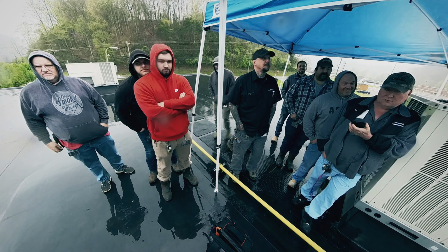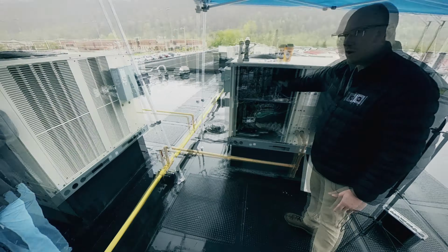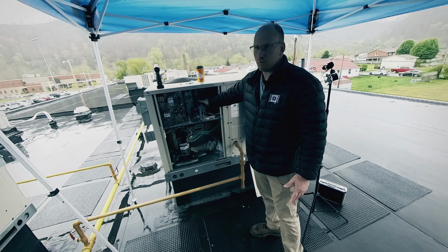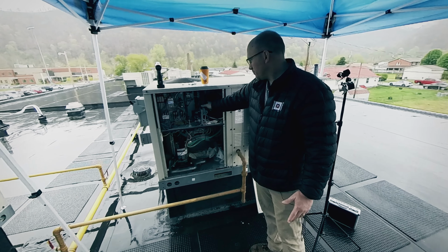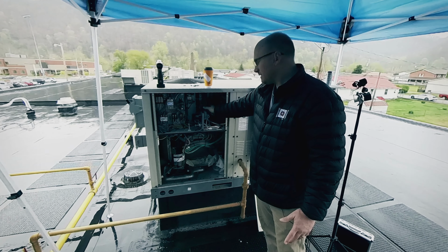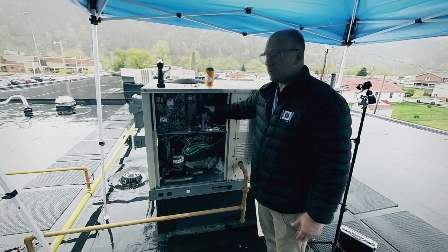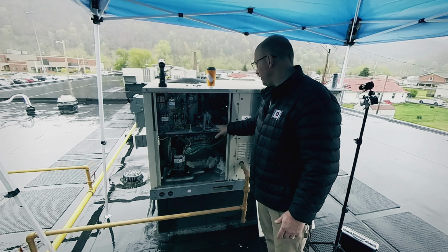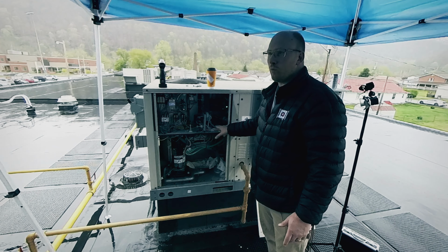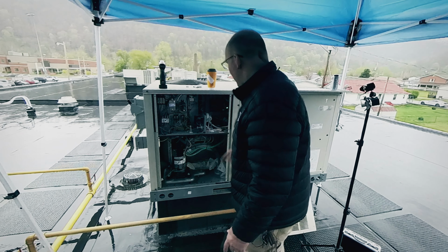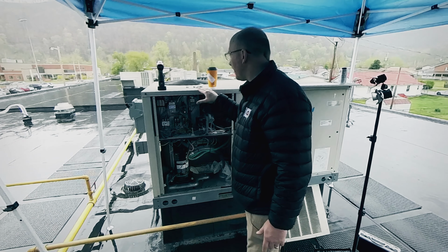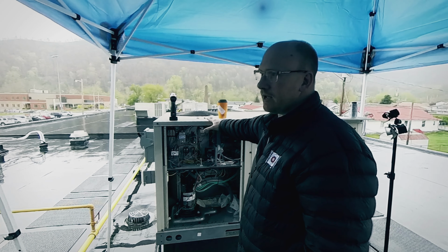All right, the controllers for these units are right here. These units do not have a Microtech, so everything's being controlled from here. It pretty much acts as a regular thermostat. It's simple. Everything goes to here. You've got your common, your red, your green, your fan, Y for cooling. These units have a low ambient control kit to control the fan in wintertime for cooling if needed.